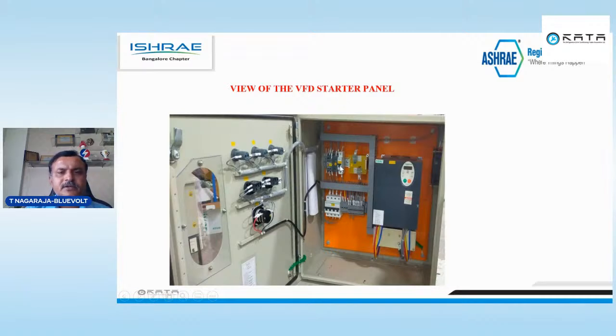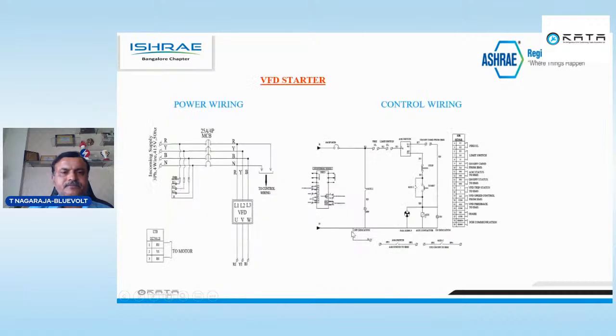Any interlocks, provisions, outside BMS connectivity, everything will be connected here also. But the only thing is, if there is any problem with the VFD, we cannot run. That will be very rare actually. Suppose 10 to 15 starters are there, or 25 VFD starters are there, we can keep one VFD as a spare. Then we can avoid a bypass also. Those things are also possibilities.